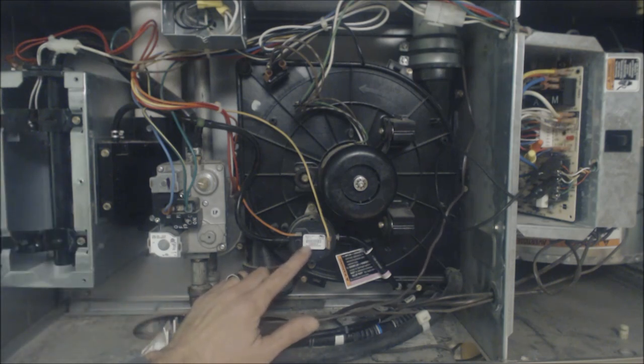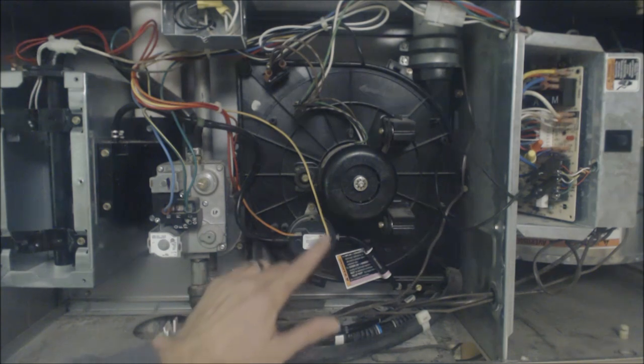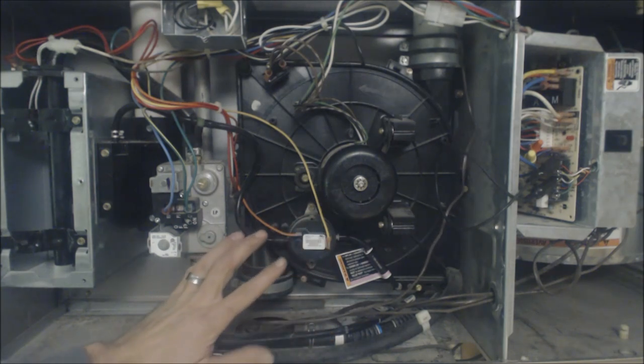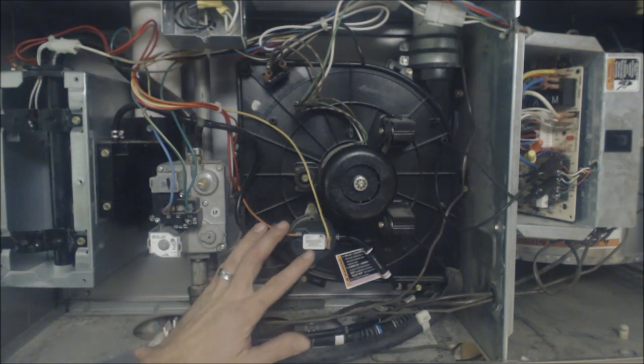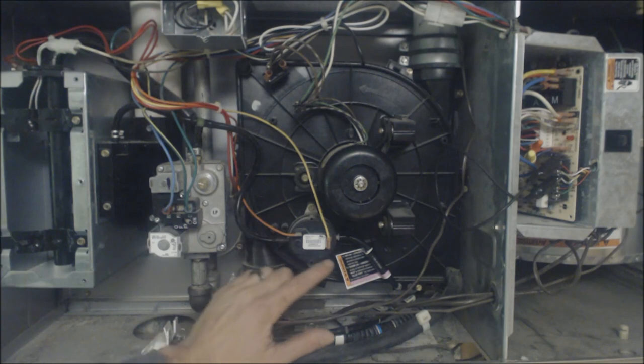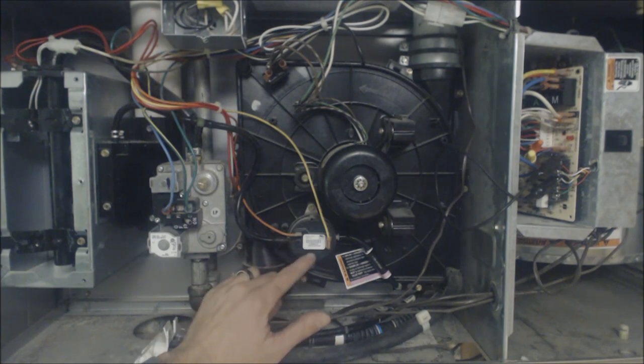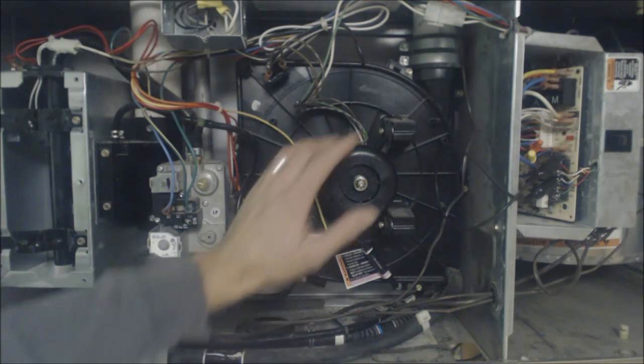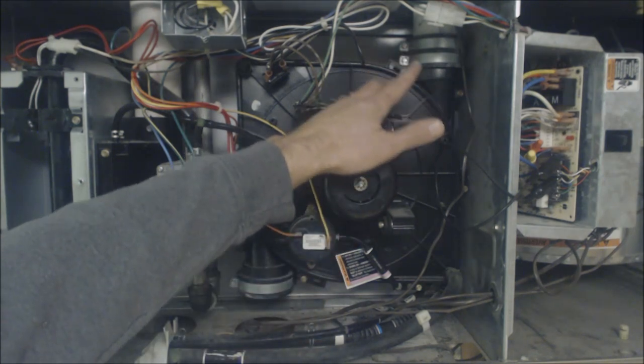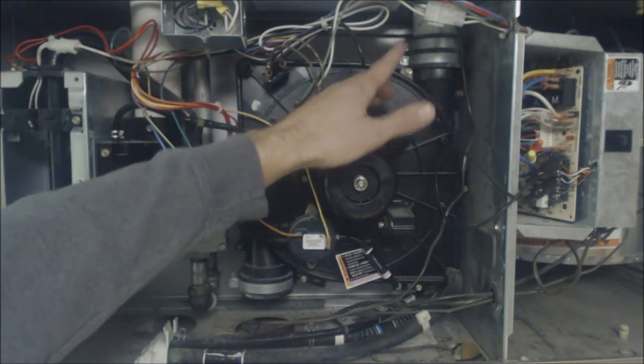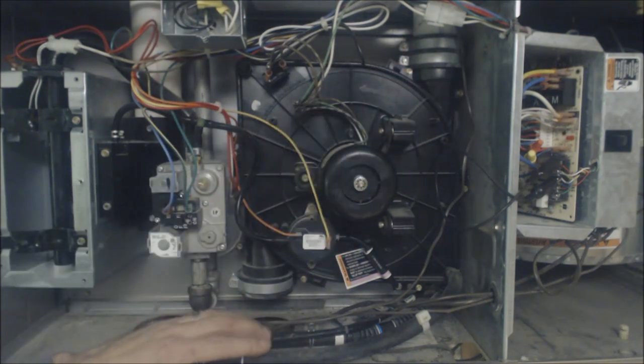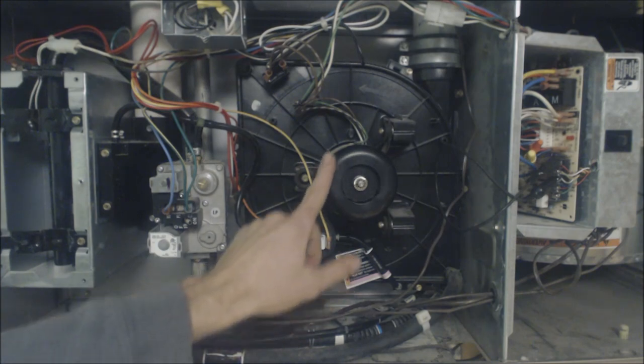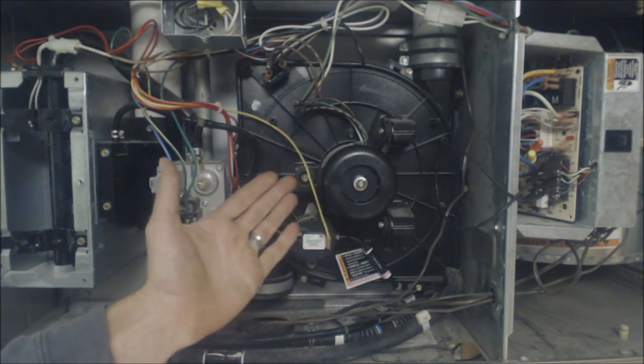Or maybe the pressure switch did not close, so this is where we're going to target right here. There's a couple things that could be the problem and it's rarely the pressure switch itself is the problem, it could be the exhaust pipe right here could have a bird's nest in it.